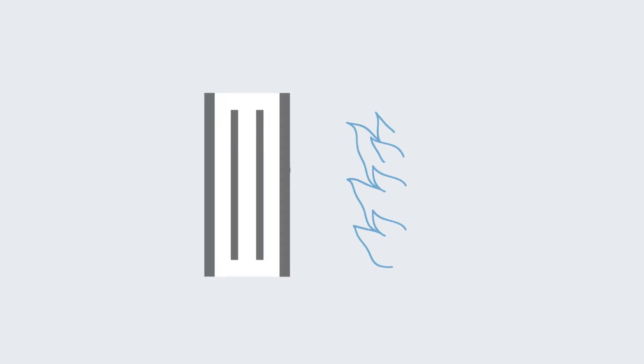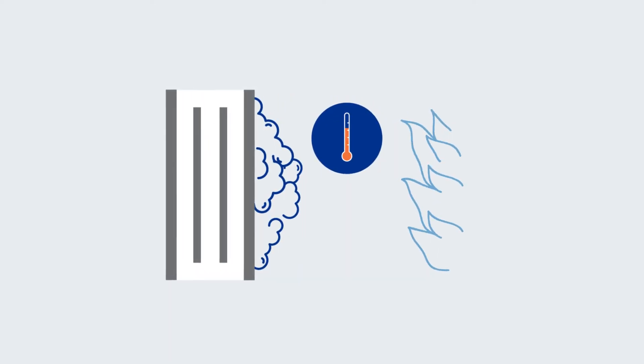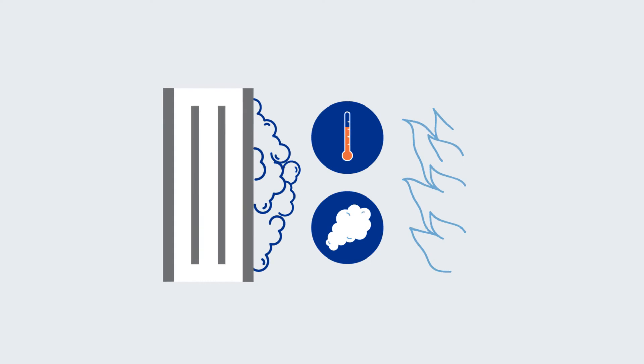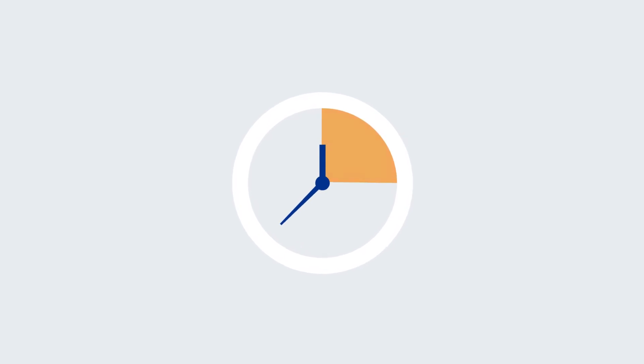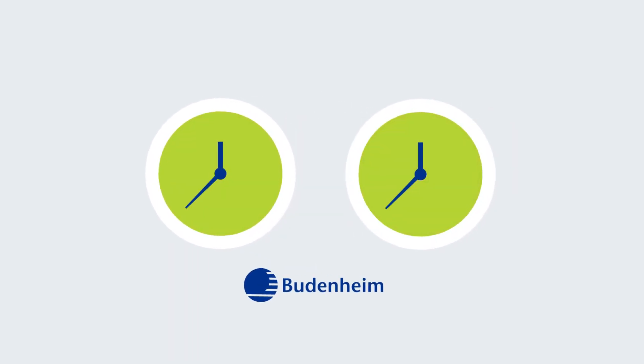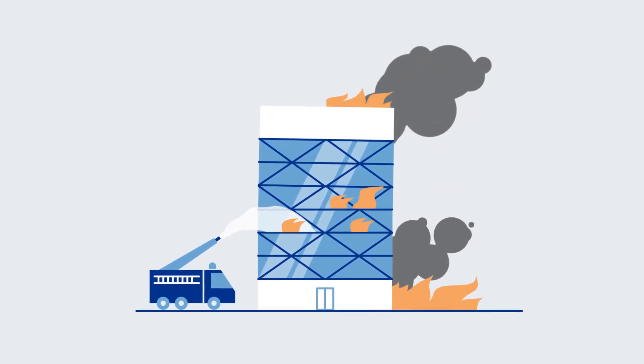When heated, an insulating foam is created that cuts off heat and oxygen and inhibits smoke. This way the steel can cope with high temperatures much longer. With the coating ingredients from Budenheim, minutes turn into hours, and give firemen enough time for saving lives and putting out the fire.